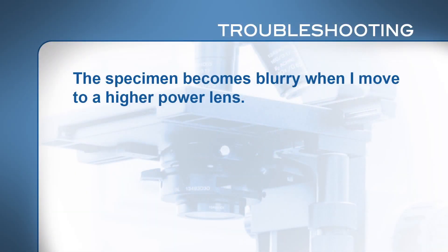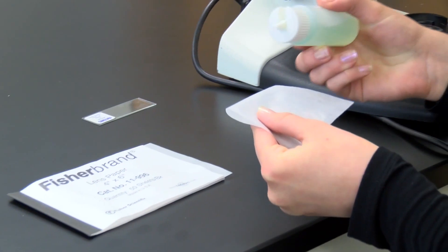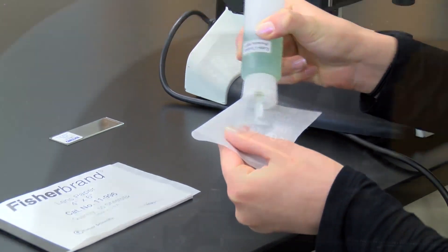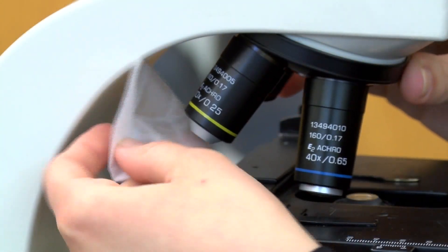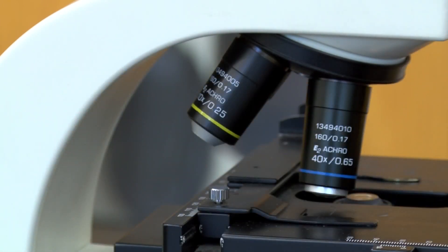If when you move to a higher power lens the specimen becomes blurry as though it were coated with Vaseline and you cannot focus, you may need to clean the lens. Soak a piece of lens paper — and only lens paper — with lens cleaner and wipe the lens. Then wipe dry with clean lens paper and repeat a couple of times. If this doesn't solve the problem, check with your instructor.